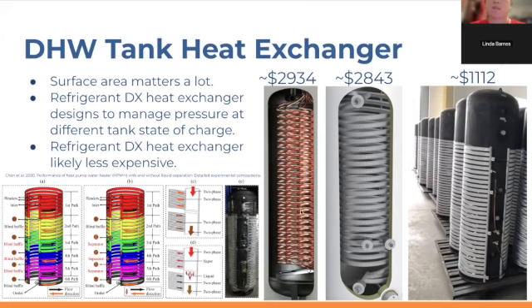And you can imagine, just looking at the picture, that building this heat exchanger and then fitting it inside the tank and then welding it so that all the connections between the heat exchanger and the outer cylinder of the tank are 100% waterproof for 15 years, 20 years, whatever the tank life is, is kind of more challenging than the far right picture, where the heat exchanger is put onto the tank like a jacket. It's simple enough, a robot can just boop, wrap the tank and then secure the bolts to keep it secured.